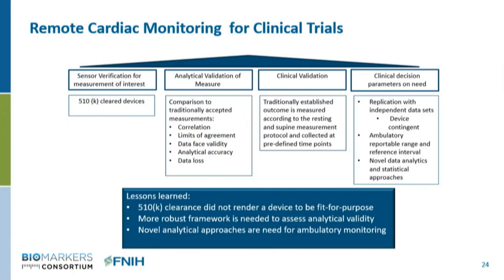To conclude with lessons learned: a 510(k) clearance does not necessarily render a device fit for purpose for use in clinical trials. More framework is needed to assess analytical validity, especially in the context of ambulatory monitoring. And as Vadim highlighted, we definitely need novel statistical approaches to analyze and interpret the data. With that, I will conclude the presentation and move into Q&A.